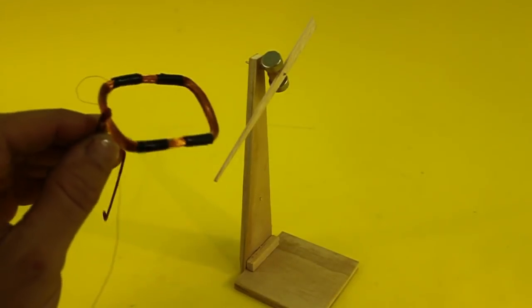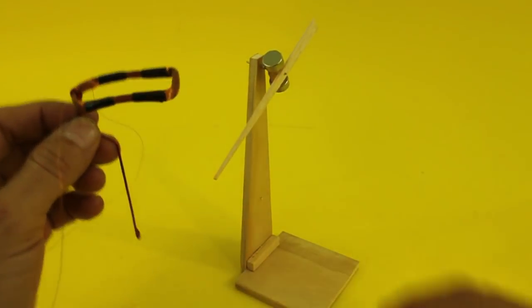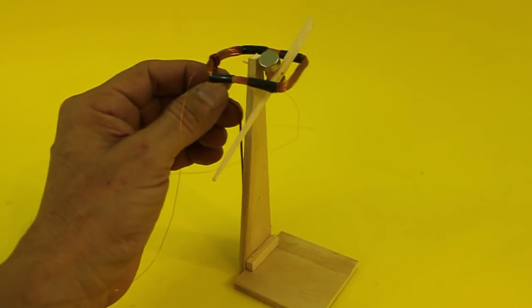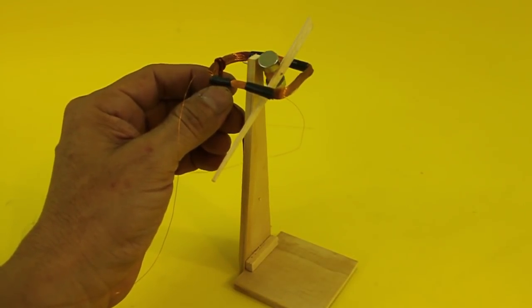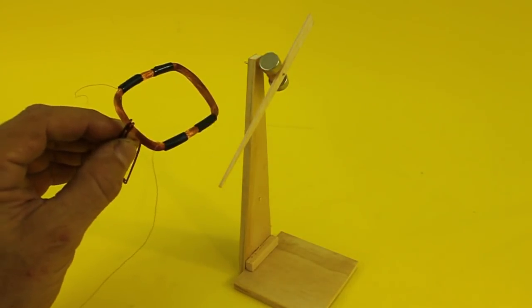The coil produces the magnetic field that makes the needle rotate and goes in this position. It is made with magnet wire size 34 and has 200 turns.